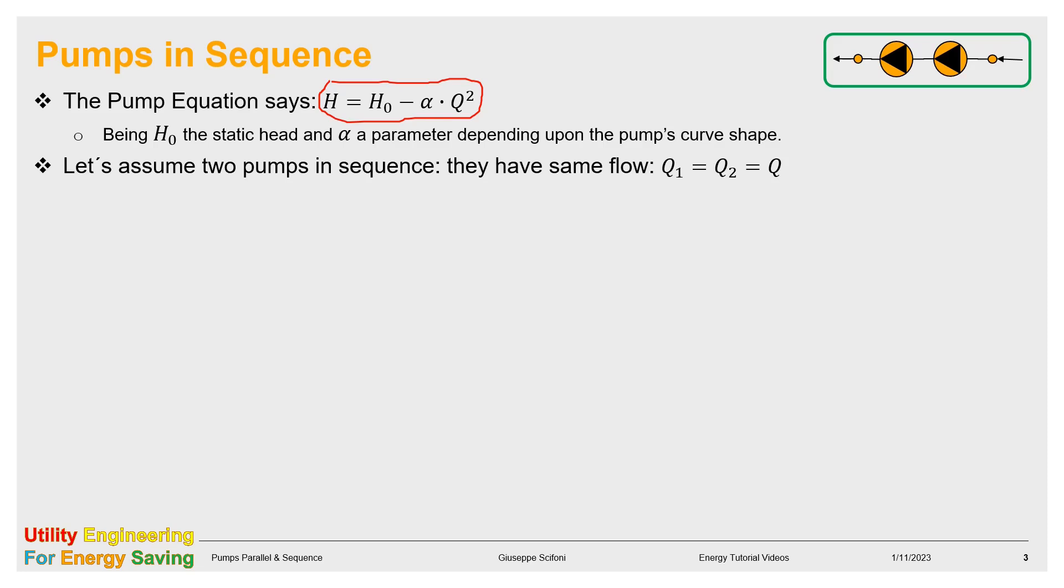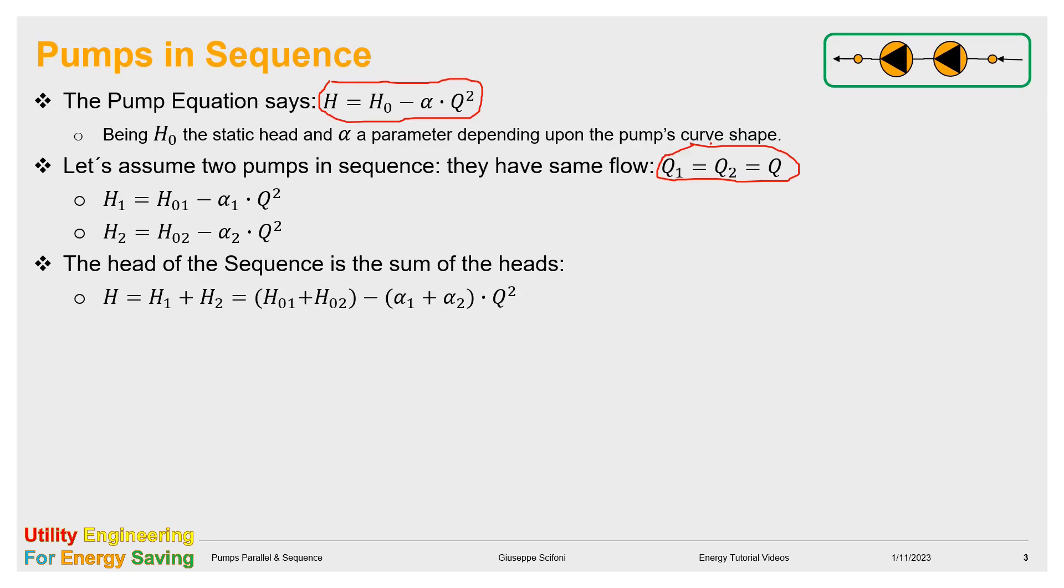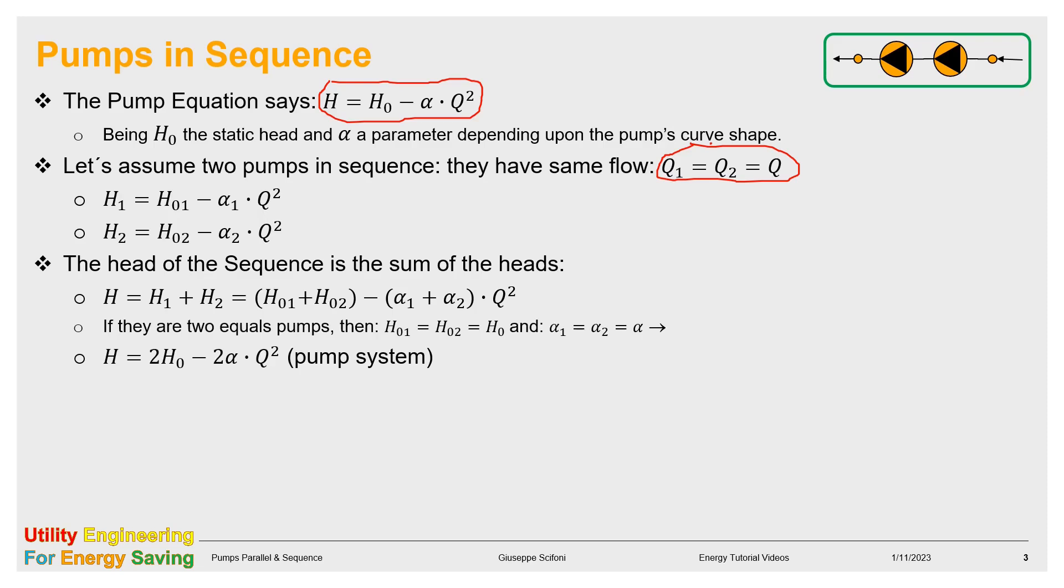Since the pumps are in sequence, they share the flow. Also, Q₁ equals Q₂ equals Q. On the other hand, the heads are added. So, we sum the two pump curves. If the pumps are equal, then the static heads H₀ and the curve shape α are the same. We obtain the curve of the new pump system. The working point is the intersection of the network curve with the pump system curve, already found.